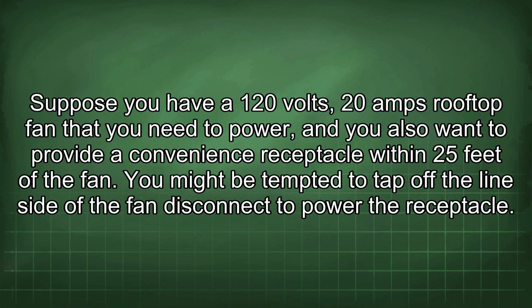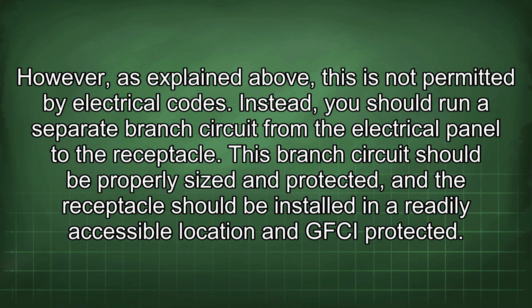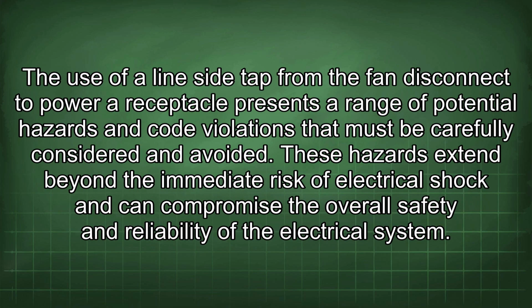Suppose you have a 120 volts, 20 amps rooftop fan that you need to power, and you also want to provide a convenience receptacle within 25 feet of the fan. You might be tempted to tap off the line side of the fan disconnect to power the receptacle. However, as explained above, this is not permitted by electrical codes. Instead, you should run a separate branch circuit from the electrical panel to the receptacle. This branch circuit should be properly sized and protected, and the receptacle should be installed in a readily accessible location and GFCI protected.